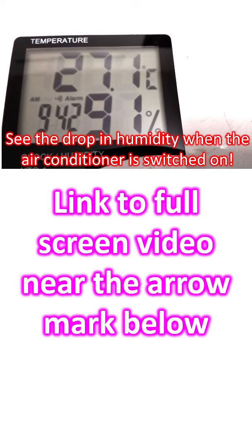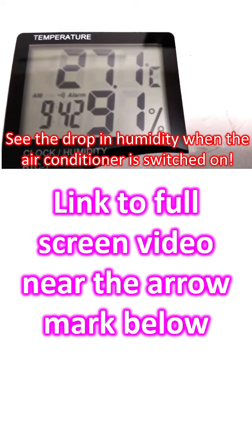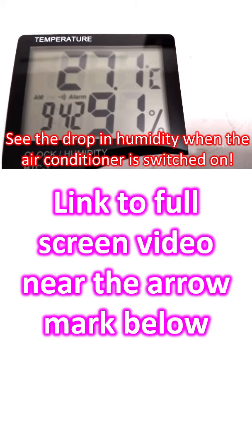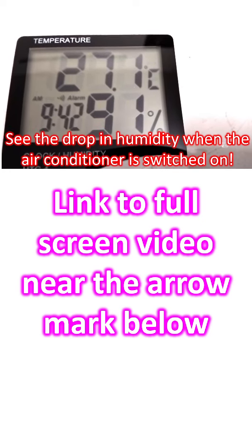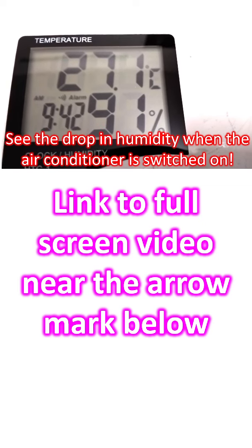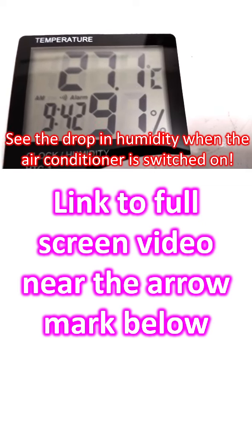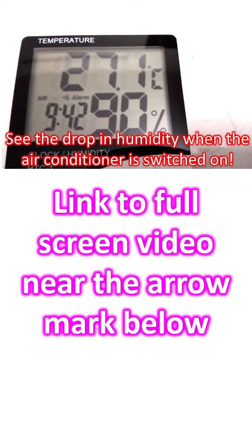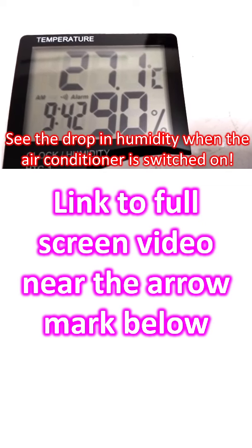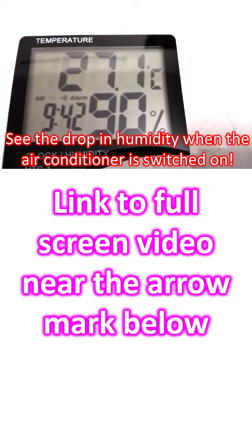Capacitive hygrometers measure the effect of humidity on the dielectric constant of a polymer or metal oxide. A calibrated capacitive hygrometer can have an accuracy of plus or minus 2% relative humidity, between 5 and 95%.